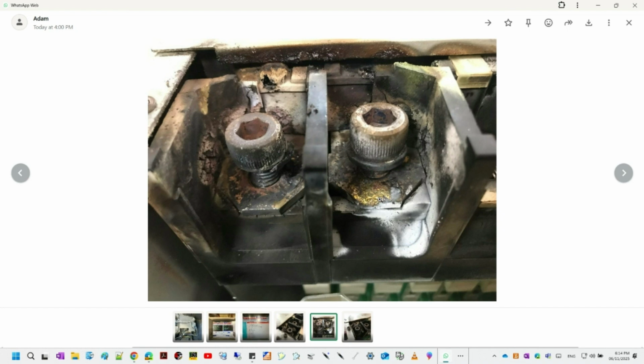Simple as that sometimes. If they weren't torqued correctly to the manufacturer's spec during installation or maybe during previous maintenance. Or vibration. Exactly, they vibrated loose over time in the machine's operating environment. If that connection isn't mechanically solid, electrically solid, you get high resistance. Contamination on the surfaces and surface oxidation also definitely contribute by increasing resistance right at those contact points. Okay, so a loose bolt, maybe some dirt, leads to high resistance.